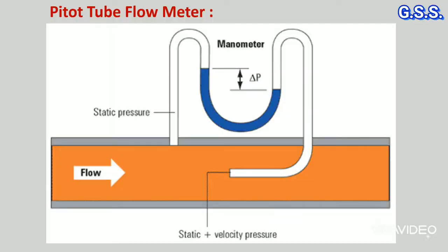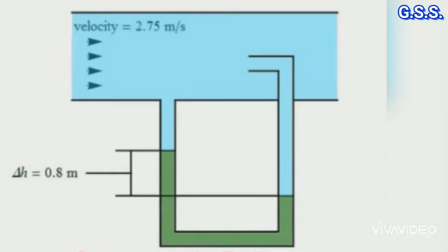Pitot tube measures the differential pressure between total pressure and static pressure. This differential pressure is directly proportional to velocity squared in the pipeline, and this differential pressure is used to measure volume flow rate. In pitot tube, pressure is generated in a tube facing the flow by the velocity of fluid.